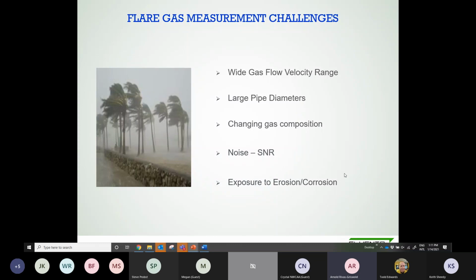So now I'd like to cover some of the challenges that we see with this kind of application. We'll go a little bit more in detail, but some of it is the velocity range is very wide. In normal operation, you have a low velocity because you don't expect to emit that much gas, but in an emergency situation, you may have large volumes of gas going to the flare line, and you have to be able to measure and account for it. Because that volume can be very big, sometimes you have to design for large pipe diameters. So that's another consideration. And of course, because the gas may come from different directions or different sources within the plant, the gas composition may vary depending on the situation or what compressor went down, what unit is in trouble. So you will have changing gas composition all the time or most of the time.